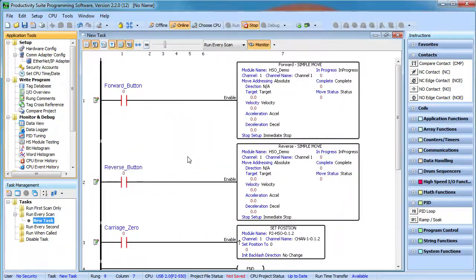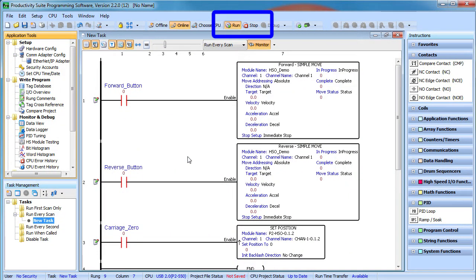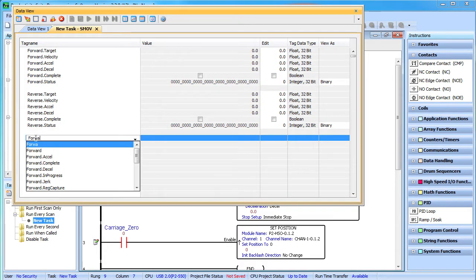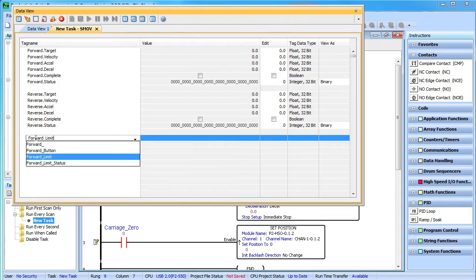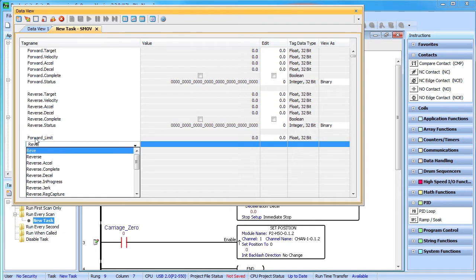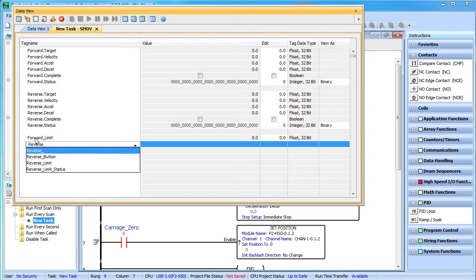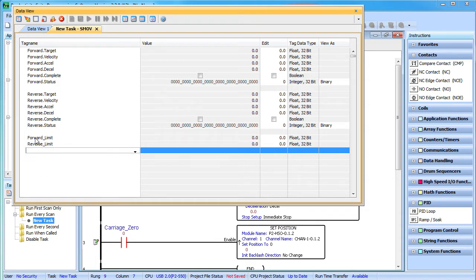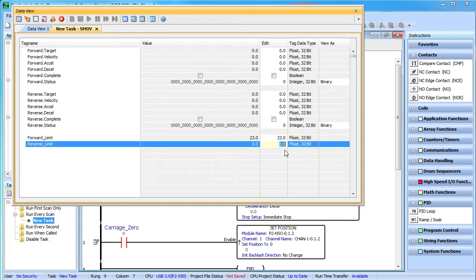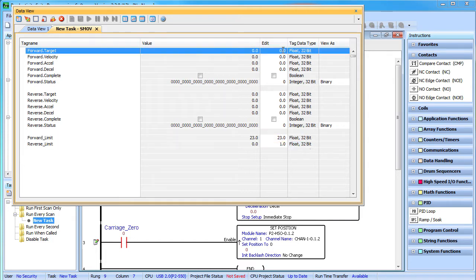I'm going to reach over and flip the switch to put the CPU in run mode and bring up a data view. I've already deleted the stuff that we don't need and rearranged things a little bit. I'm also going to add the positive and negative direction limit tags which we defined in the hardware configuration so we can modify those. We have a 24 inch slide so let's make our positive direction limit 23 inches and a negative direction limit 1 inch.